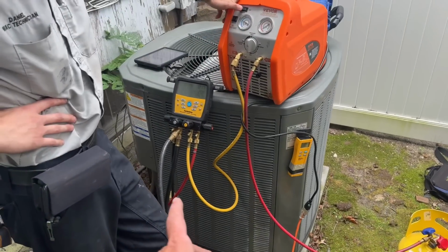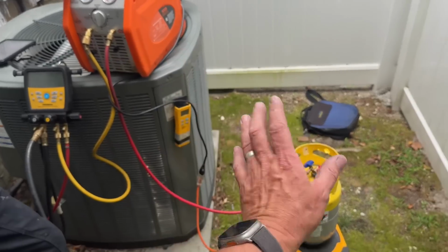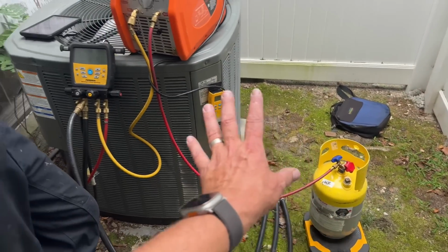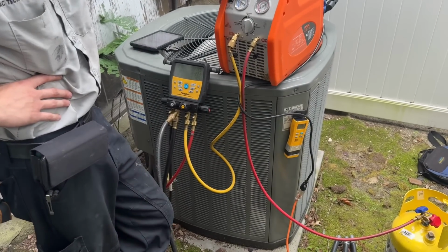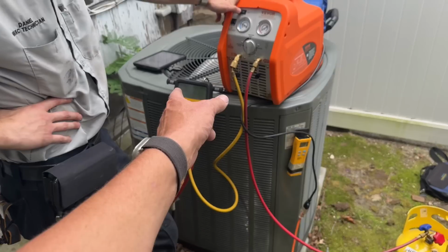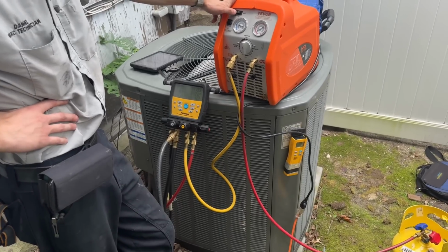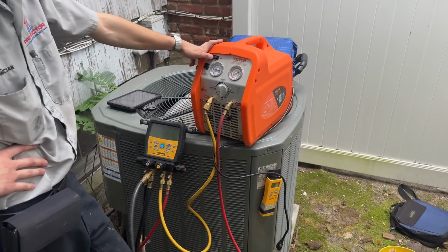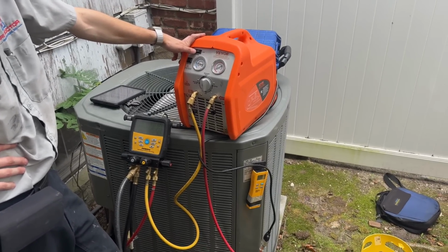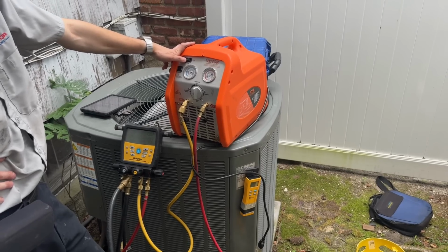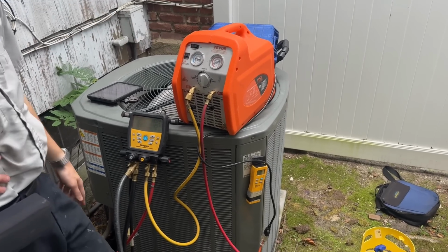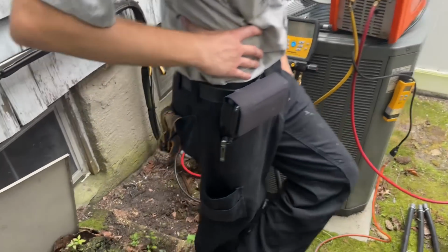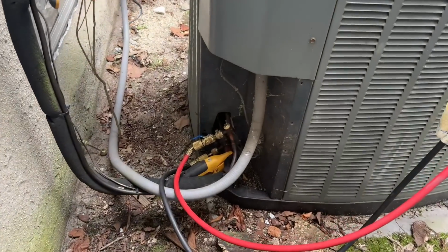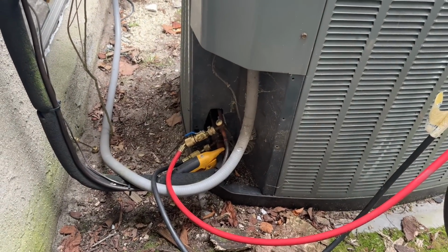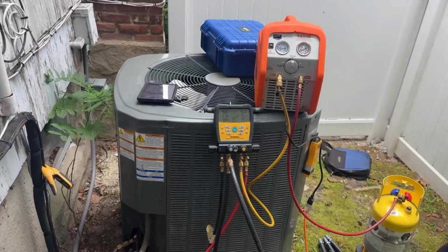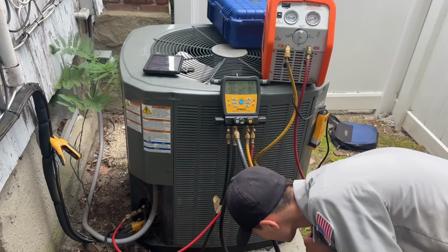So right now, we're just recovering off vacuum alone the refrigerant that's in this system. And we are at 121 PSI and dropping. Daniel just turned on the recovery machine. We have our Schrader cores pulled on the high side. We're going to pump down, and then we're going to replace that TXV.